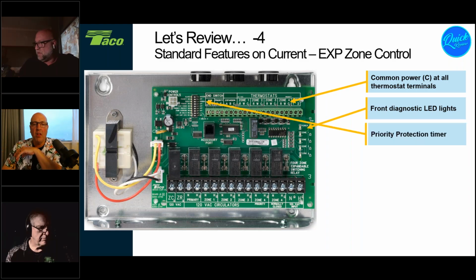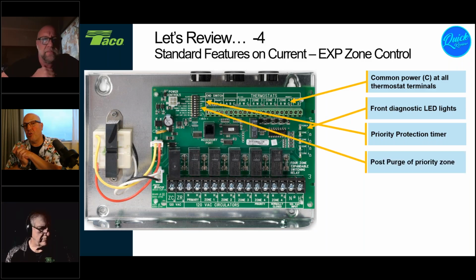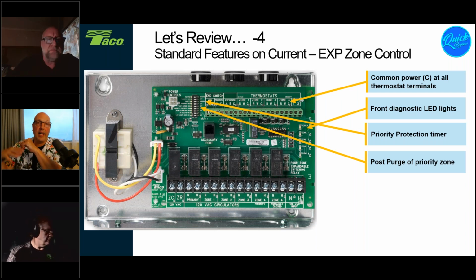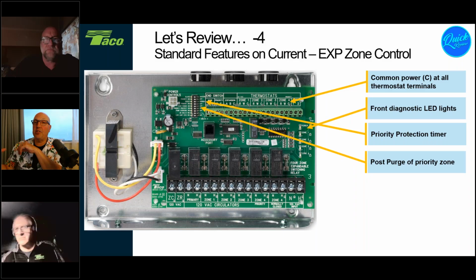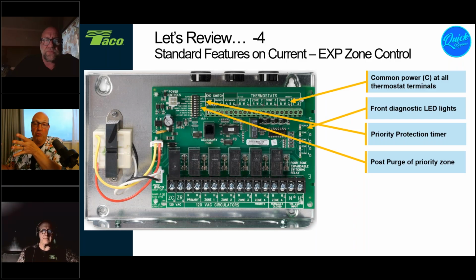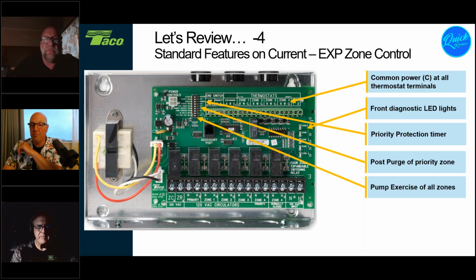And then these dip switches that were here gave us some extra functionality like priority protection, or priority on, if there's a zone you want to designate as a priority zone. We also set up post-purge, meaning, hey, last zone calls for heat, let's take the BTUs out of the boiler and dump it, say, into the indirect tank. This way, because the tank's going to hold heat, a better thermos than, say, our boiler is, let's put the BTUs there. And we could also do pump exercise.